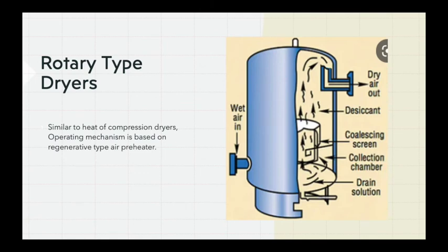In the second cycle, which is the cooling cycle, the air which is coming from the compressor at a temperature of 135 degrees Celsius is made to pass through the aftercooler. Once it passes through the aftercooler, then it goes to vessel B, which is in the regeneration mode, and helps to take all the heat which is present in the vessel and thus helps to cool the vessel.